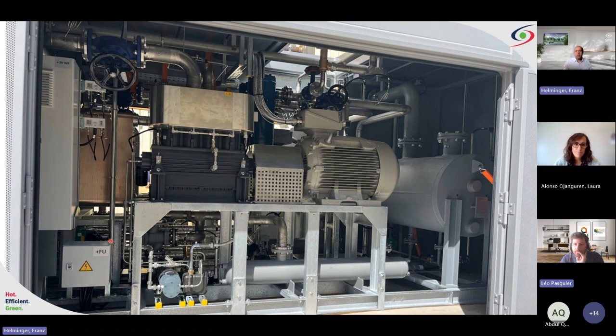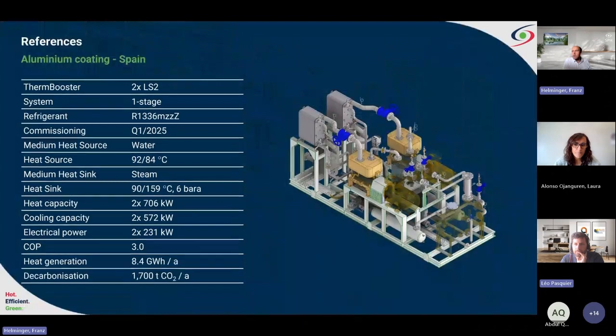I want to draw your attention to another project where we deliver two LS2, that means liquid to steam, with another refrigerant due to higher temperatures of the steam. We are using there the 1336 MZZZ refrigerant and generating steam up to nearly 160 degrees C by using a heat source from inlet 92 to outlet 84. It's already very high inlet temperatures. And we end up, for one machine, with around 700 kilowatts of heating capacity and a COP of 3.